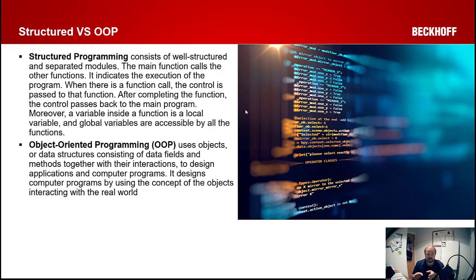Your main program calls your safety program, your safety program is then in control, that passes back to your main program which then calls the motion program that runs the motion for the machine and so on. That contains a mixture of local variables, so each program has its own set of variables, but then you need to pass data between them and that's when you start using global variables. That can be problematic because if you don't do that correctly, you can change things in one program that another one needs and give yourself a headache.